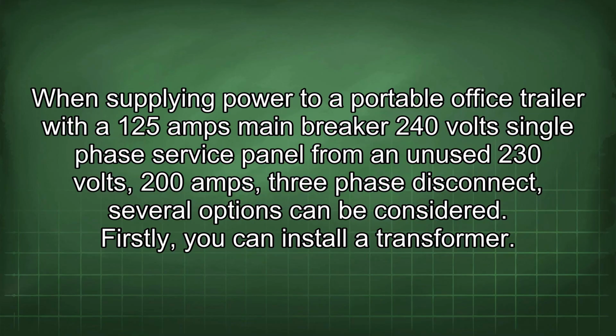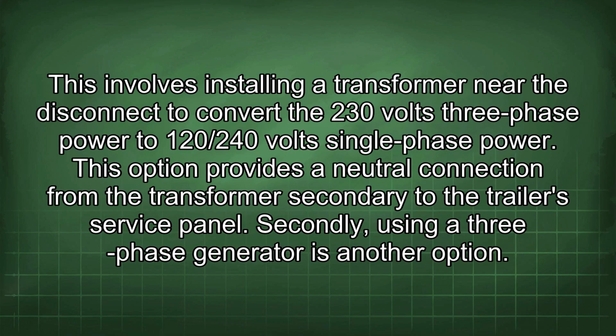When supplying power to a portable office trailer with a 125 amp main breaker, 240 volt single-phase service panel from an unused 230 volt, 200 amp, three-phase disconnect, several options can be considered. Firstly, you can install a transformer. This involves installing a transformer near the disconnect to convert the 230 volt three-phase power to 120/240 volt single-phase power. This option provides a neutral connection from the transformer secondary to the trailer's service panel.